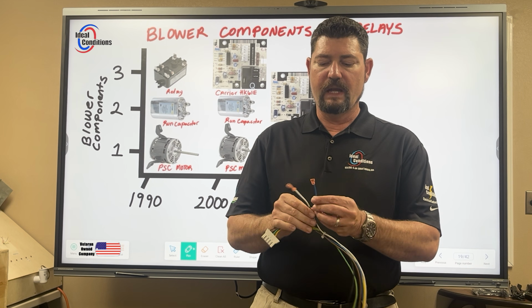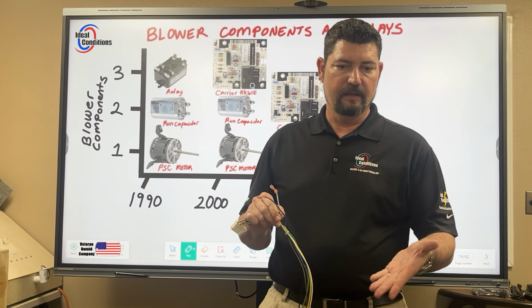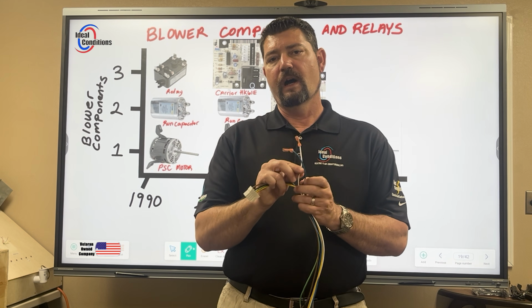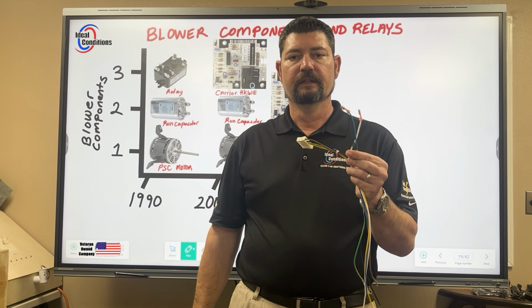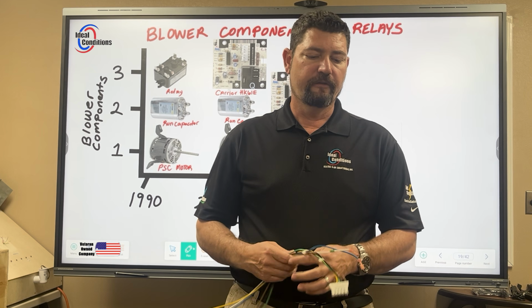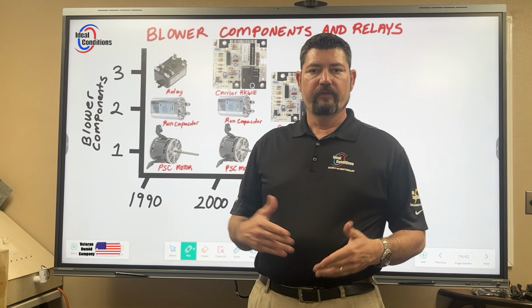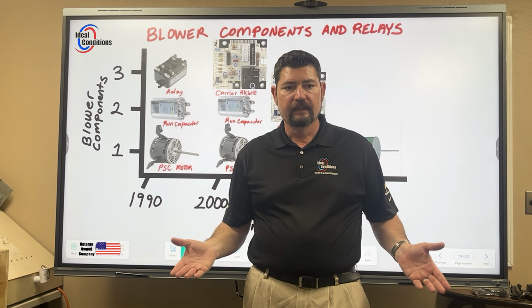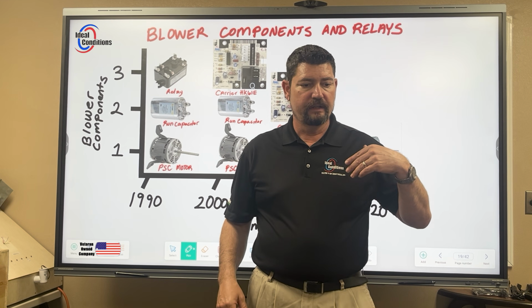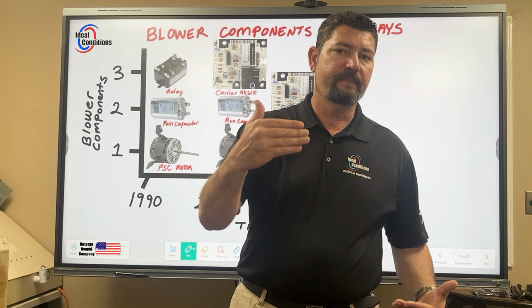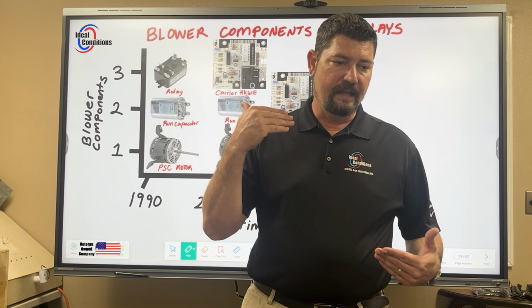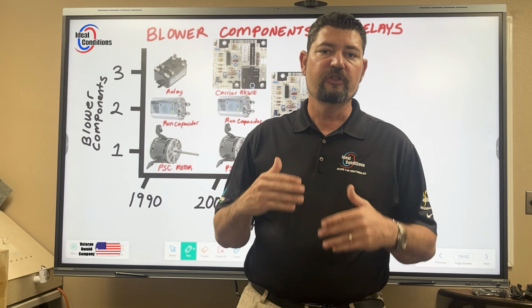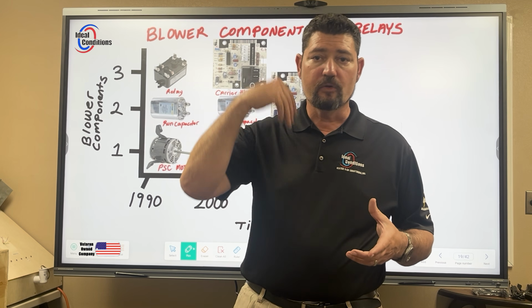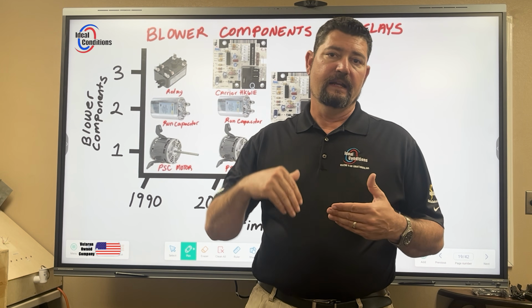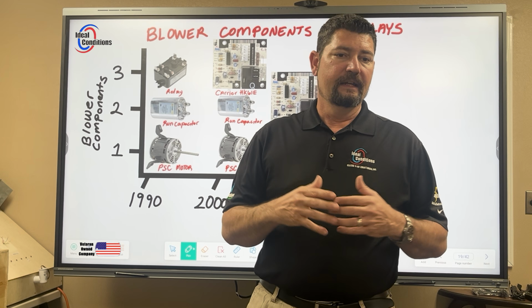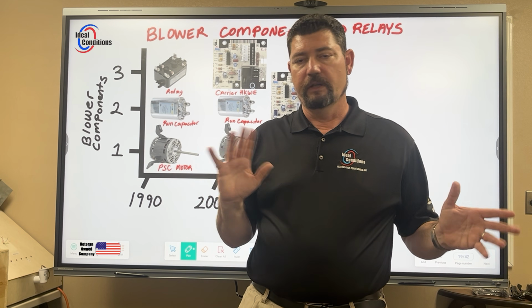The other two wires that we haven't gone over yet, the blue and the white, we went over at the perspective of wiring it up. These two wires are for two different speeds, okay? The reason why we have two different speeds is in our trade, we have typically more than one stage of heat. And in the event that we have to run at a higher CFM, we need to be able to pick up that speed. So when we get that additional call beyond just the call for a fan motor, like if I'm running a fan motor with the heat strips, okay, then I'm gonna have to bring my CFMs up. So now if I'm just wired to medium speed, it'll work on everything, right?